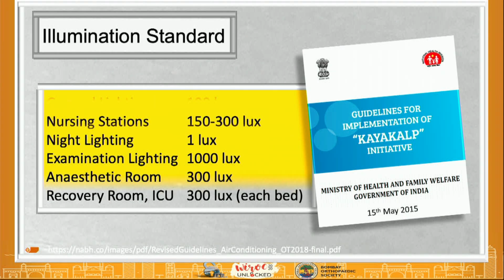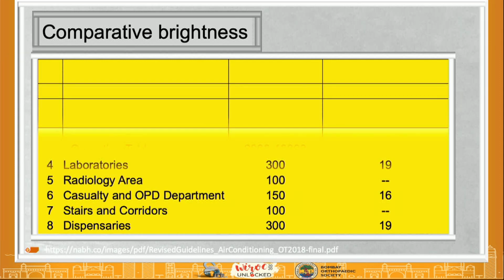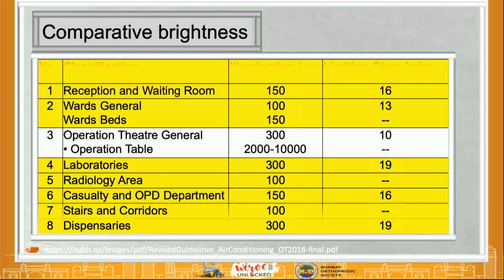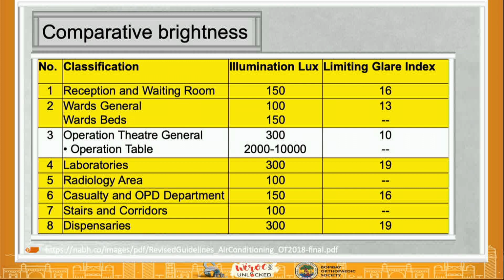Ministry of Health and Family Welfare has come out with this guideline that what should be the light in our overall hospital. So there are different areas in hospital where it starts from 1 lux to 300 lux, but it's very important for us to know that this is much different for operation theater in general, which is outside the table, that is 300, but on the table it should be from 2000 to 10,000, where we are using too high, where the recommended lux is very low.